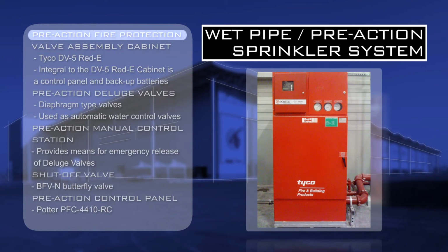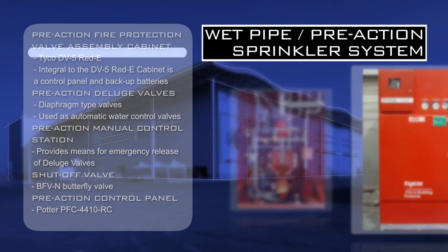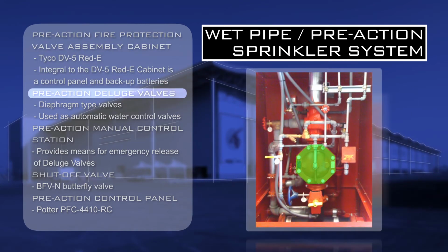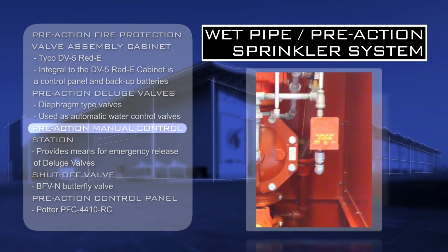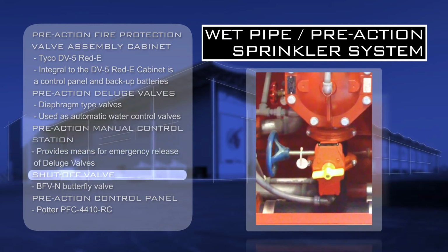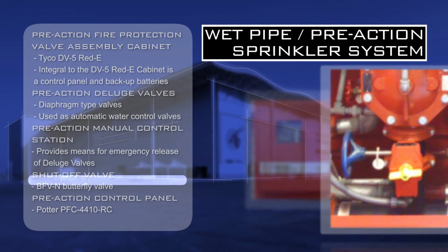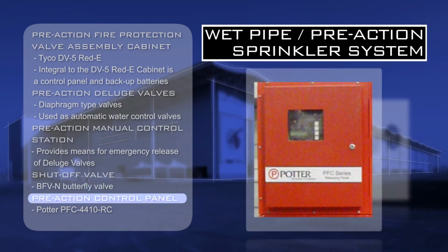Pre-action fire protection comprises the valve assembly cabinet, which is red and has an integral control panel and backup batteries. Pre-action deluge valves, which are of a diaphragm type and used as automatic water control valves. The pre-action manual control station, which provides emergency release of the deluge valves. Shut-off valve, which is a BFVN butterfly valve. And a pre-action control panel.